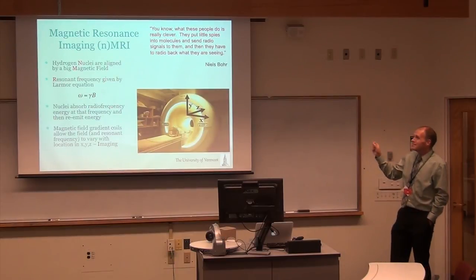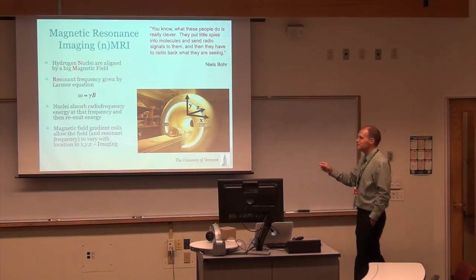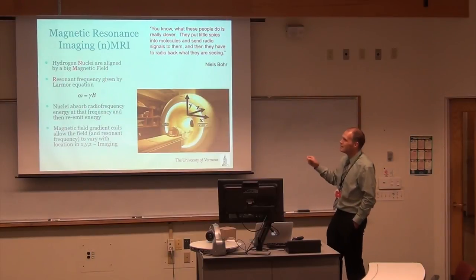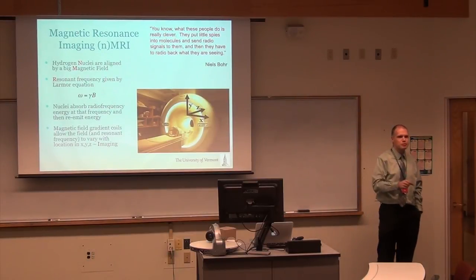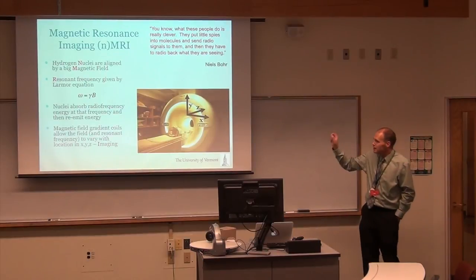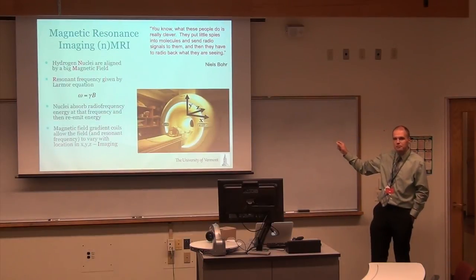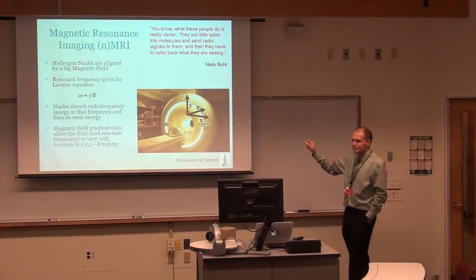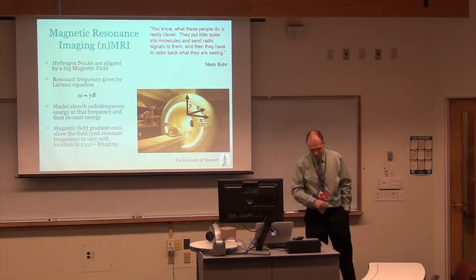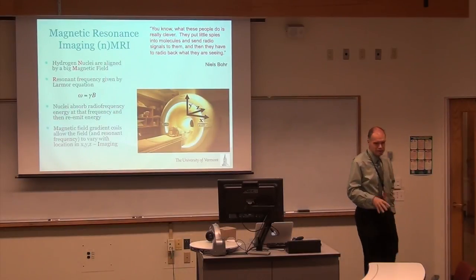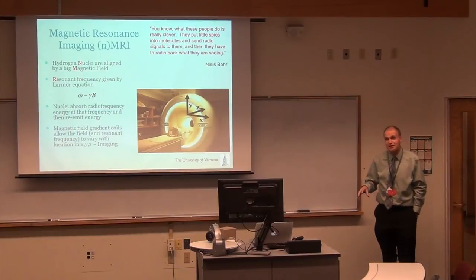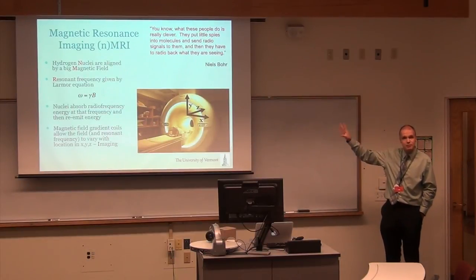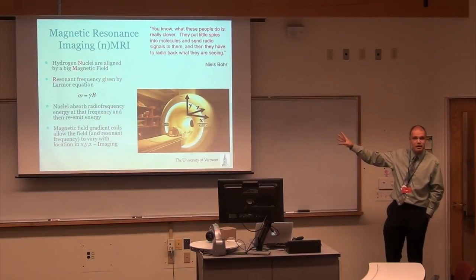If you put hydrogen nuclei into a magnetic field, they resonate. They have a resonant frequency, nuclear magnetic resonance, and this resonant frequency is proportional to the magnetic field strength. The resonant frequency omega is proportional to B, where gamma is the gyromagnetic ratio, a constant for hydrogen nuclei. It's 42 megahertz per Tesla, which means in a 3 Tesla field, the resonant frequency is about 128 megahertz.